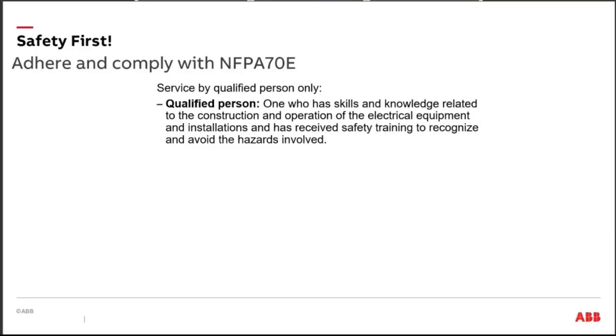When you're talking about sending somebody out to work or service a drive, we need to make sure that's a qualified person or the right person. I get that word qualified from NFPA 70E. That person is somebody that's got skills and knowledge. They know how the drive is constructed, they know about the equipment itself and the installation. They've had some safety training, and they know how to avoid the hazards.